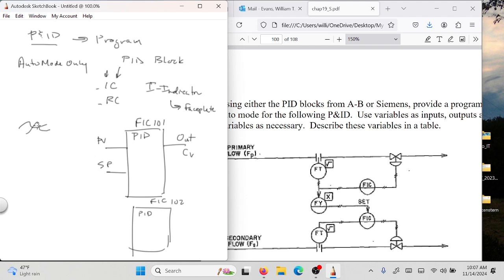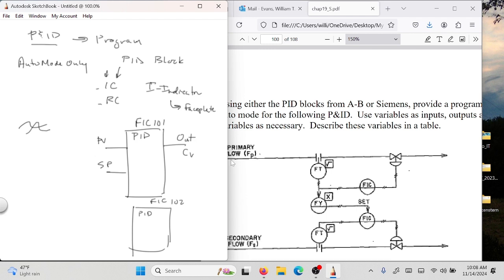4 to 20 milliamp current is your best chance of getting a signal from here to there without having noise. What's better than that? Going up to the actual device with a coax or Ethernet cable. If you can hit it with Ethernet, you win. But if you can't, use 4 to 20. And by the way, they're doing this wirelessly now — you transmit the signal from your computer to a wireless valve and it does whatever you tell it to do.